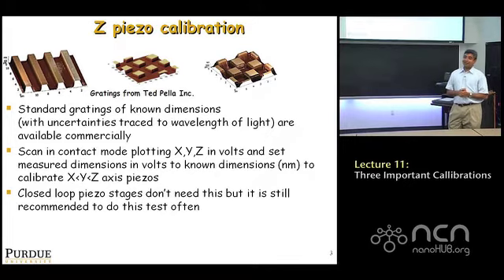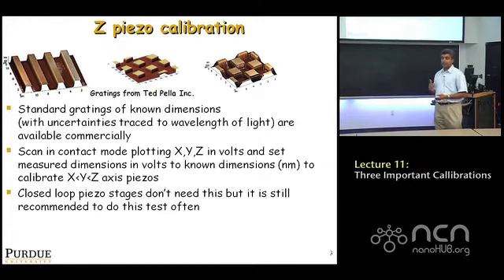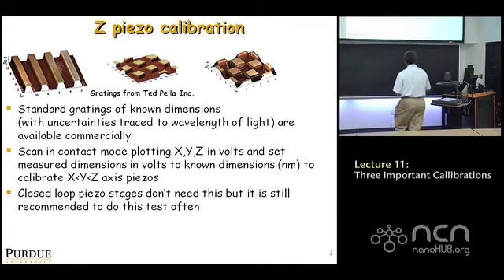At the same time, you know what problem happens if you trust too much in technology. If you trust too much in technology, the problem is when it fails you, you don't know it, right? And you keep going. So even though you use closed loop, the idea is every 6 months, my suggestion would be to calibrate these things. Because what if the sensors that are embedded inside these feedback loops stop working? How do you know? You never know. So I think you still have to, every 6 months or at least a year, do this kind of calibration, even if you have closed loop systems, okay? So everyone clear about Z piezo calibration and XY piezo calibration using calibration gratings, yeah?